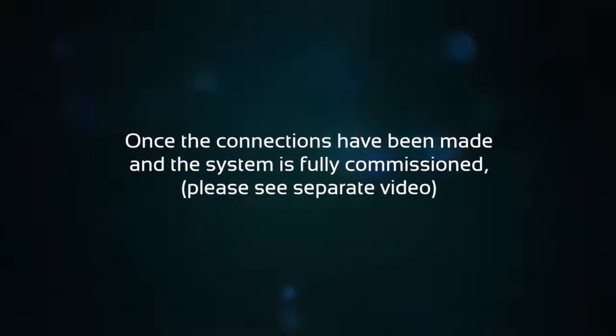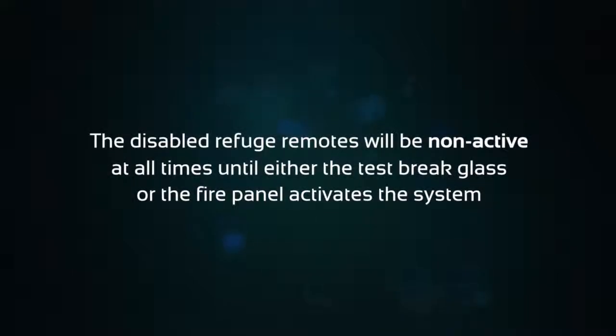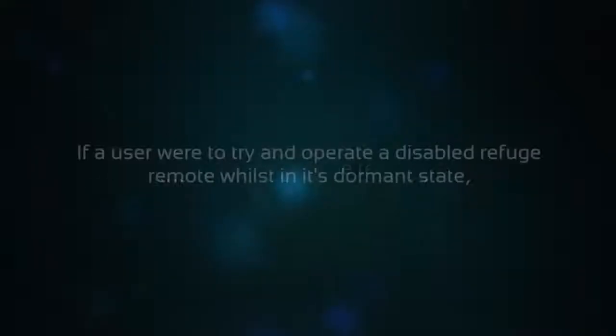Once the connections have been made and the system is fully commissioned — please see the separate video for the commissioning procedure — the disabled refuge remotes will be non-active at all times, until either the test break glass or the fire panel activates the system.